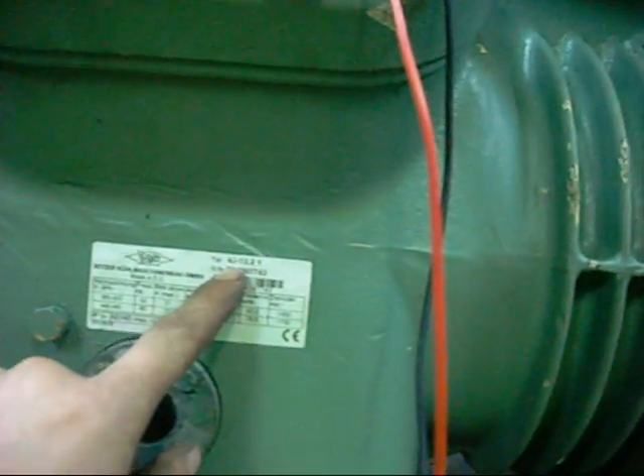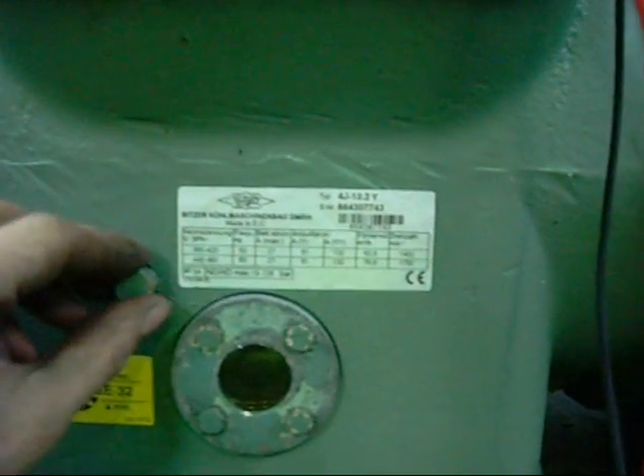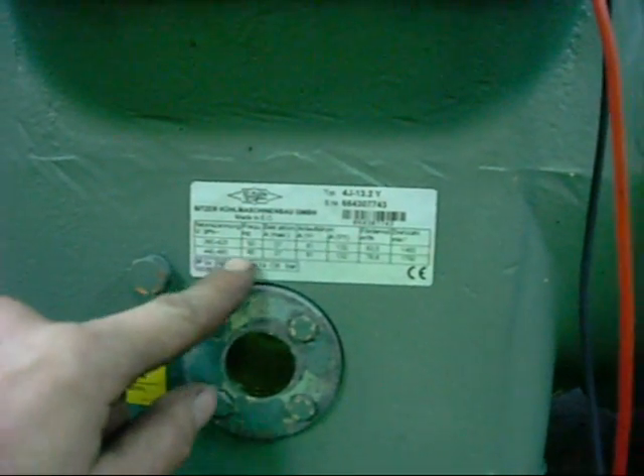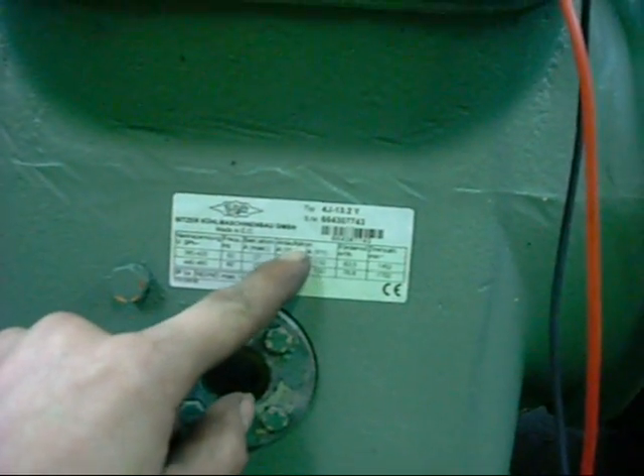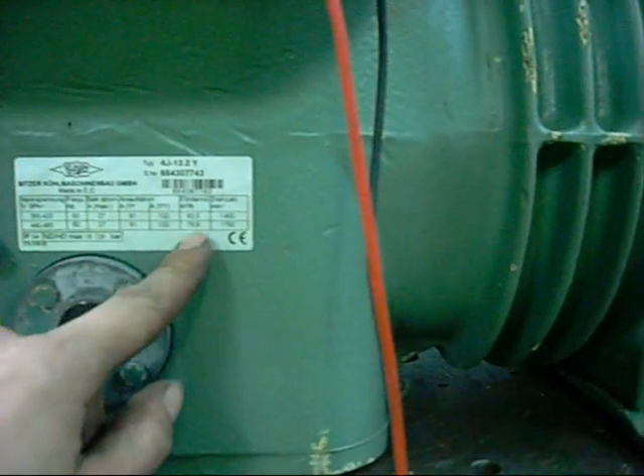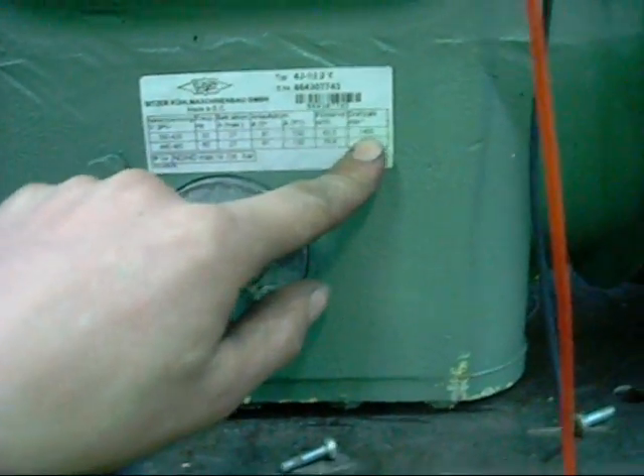Now on with the troubleshooting. Just for the record, this one is a Bitzer 4J-13.2Y, made in Germany obviously. 'Bitzer Kühlmaschinenbau' — I'm guessing that means Cool Machine Makers or Refrigeration Machine Makers. 380-420V or 440-480V, 60Hz; top one's 50Hz. 27A nominal running current, 81A locked rotor current in direct-on star configuration, or star-delta — 132A. 63.5 m³ per hour of compressed refrigerant, 1450 motor RPM on 50Hz anyway. It's a dual-spec motor — it'll run on 50 or 60Hz.